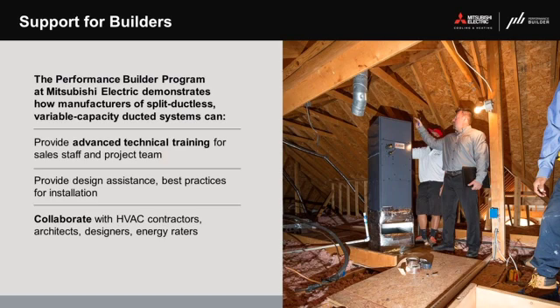A simple application an HVAC installer might recommend used to be 1 ton of conditioning for every 400 square feet of area. Today we can do 1,200 square feet with 1 ton of conditioning or even more, so that old rule really doesn't work anymore. We have to be very specific and ensure a good design, and then we get optimal efficiency, optimal air quality and health, and a product that lasts.